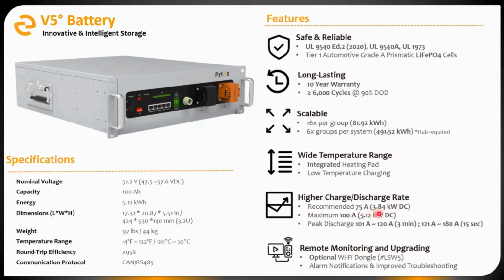To get this 1C charge rate requires a special firmware update. Most of the time, we find the 75 amp charge rate is perfectly fine, given how scalable the batteries are—if we need more charging or discharging current, it's as simple as adding more batteries to achieve that value. So the 1C rate is reserved for very special or specific cases, since it has the potential to shorten the lifespan of the battery. We like to keep it at the 75 amp rating as much as possible.